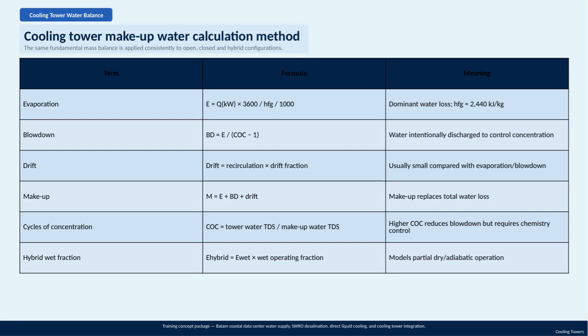Here, we're focusing on the cooling tower water balance and the method used to calculate makeup water requirements. The key principle is a fundamental mass balance, which applies uniformly across open, closed, and hybrid cooling tower systems. Let's break down the main components listed in the table. First, evaporation represents the dominant water loss in the cooling tower process. It's calculated based on a heat load in kilowatts, converted to the latent heat of vaporization, with hfg approximately 2,440 kilojoules per kilogram. This loss is significant because it directly reduces water volume in the system.